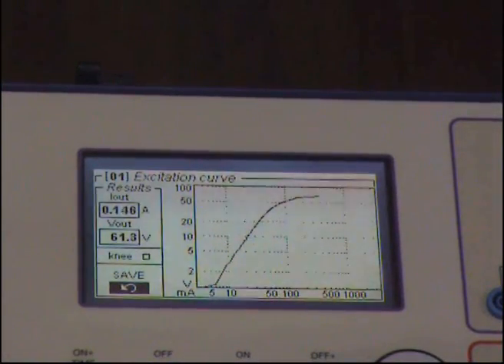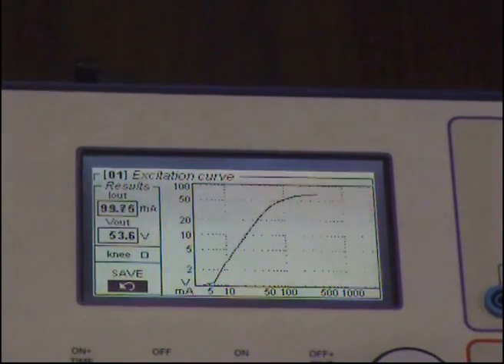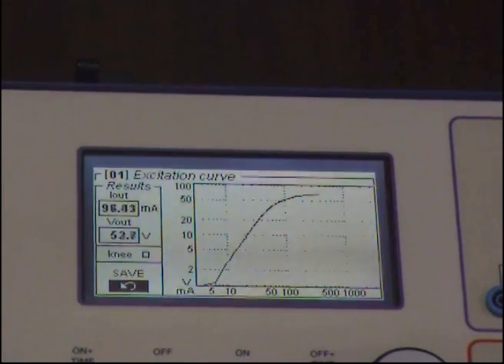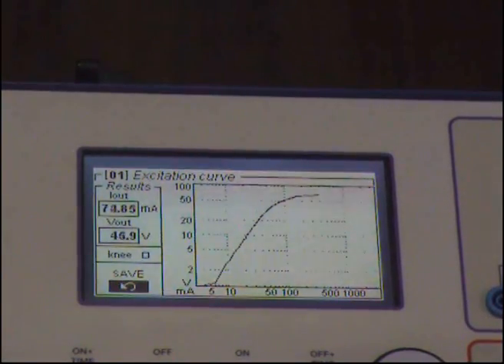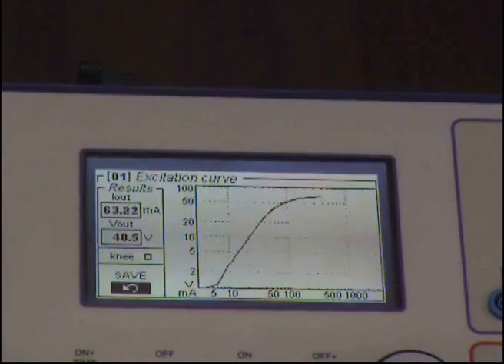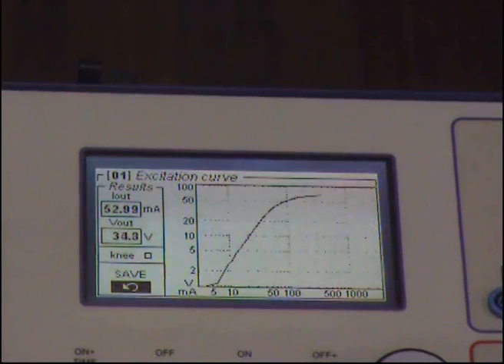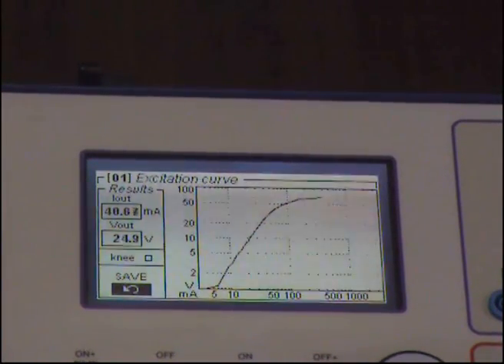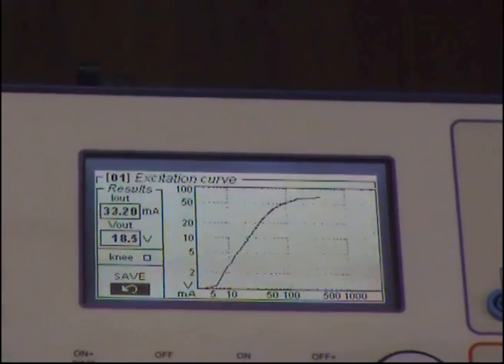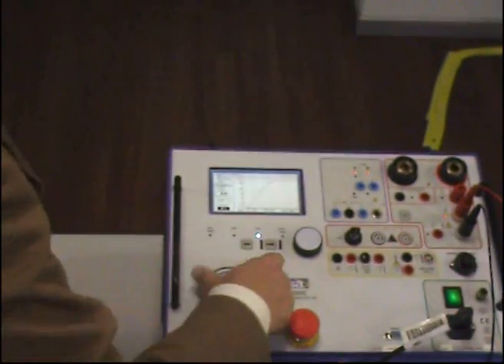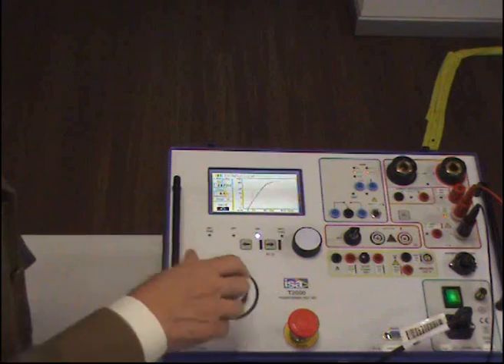Do it slowly because, as you have saturated the transformer, if you don't go slowly you leave some remnants in the core — in the iron of the transformer. This is not good, because that magnetic energy that you are leaving will cause some trouble when the current transformer is put back into service, as that energy has to be cleared before the current transformer returns to normal operation.